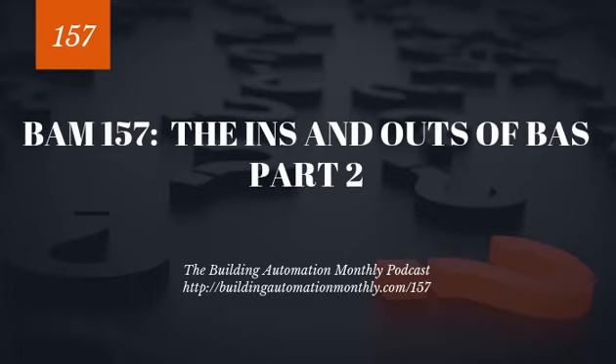So being able to signal, especially when you're utilizing a star pattern, which is basically an end-to-end run, the ability to have full bandwidth focused on a single controller versus shared bandwidth, as we see in serial protocols, is definitely a big benefit. Now, typically on these serial protocols, we rate their speed in baud rate, which is essentially a measurement of the change of state of the electrical signal.